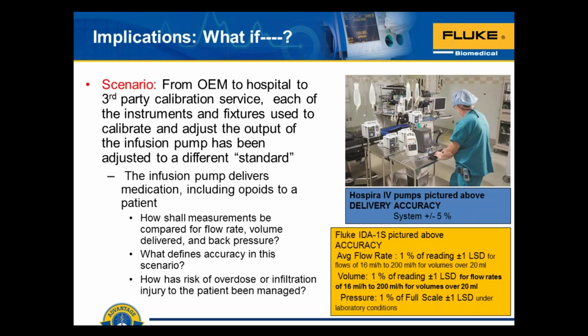Let's take a look at a what-if scenario. We get from OEM to hospital to third-party calibration service, each of the instruments and fixtures used to calibrate and adjust the output of, for example, an infusion pump has been adjusted to a different standard. That's our scenario. So in other words, there's been a different transfer standard that's been used. And so our concern is, how accurate are we really?